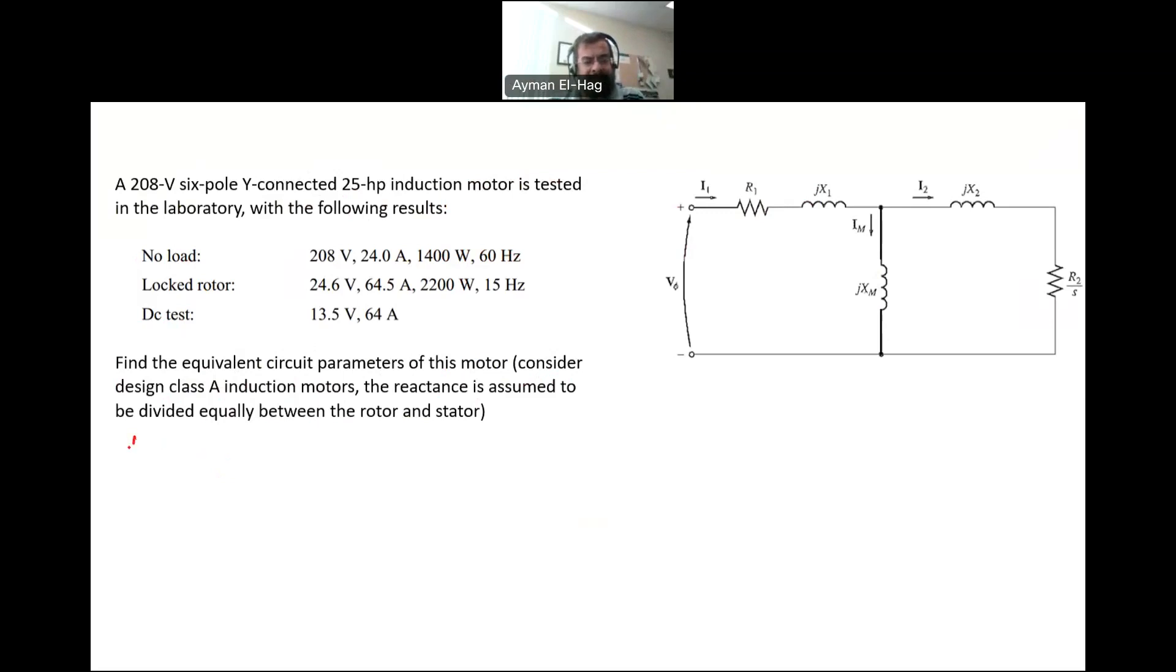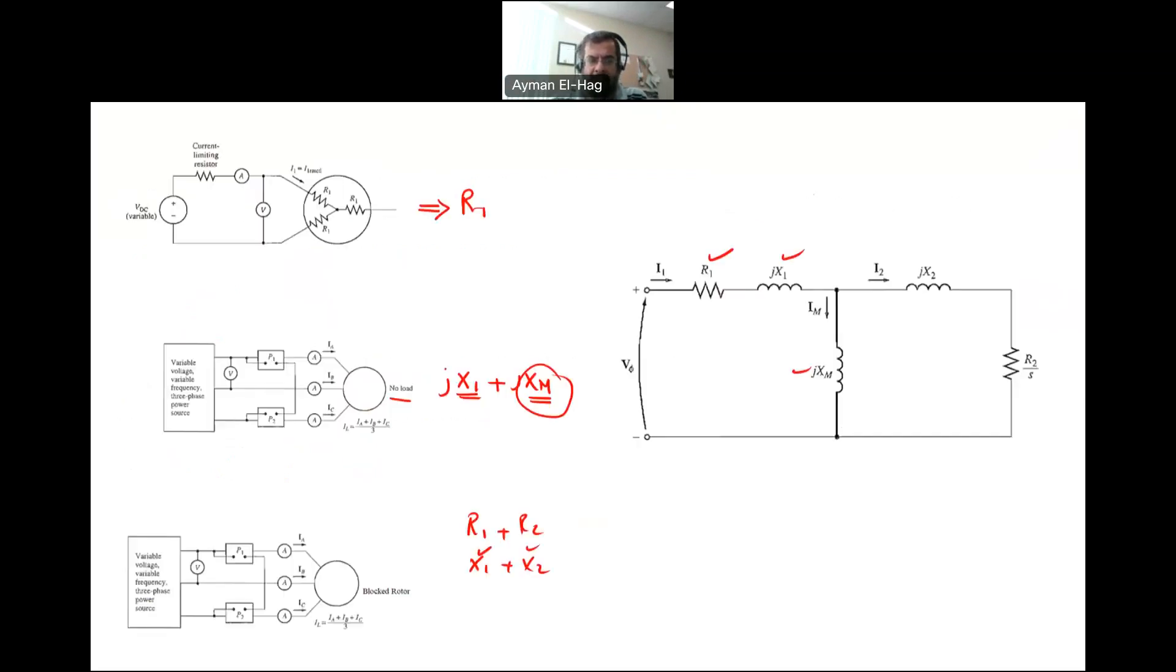We'll start with the DC test. As we mentioned, in the DC test we will be able to find R1. Since this is a Y-connection, 2R1 equals VDC divided by IDC. When we connect the DC between two terminals, it will have two of the resistors in series.